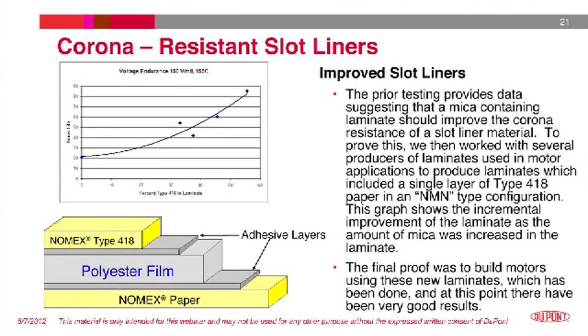We then worked with DuPont customers who already produced NMN laminates, and they produced a series of laminates where one layer of the NMN was replaced by Type 418 paper as a finished commercial laminate. This chart shows the incremental improvement seen in these laminates. Commercial motors were then built with versions of these improved laminates, and the good news is that there have been no failures to date. The bad news is that there have been no failures to date, so we don't know how much better these motors are than motors insulated with other slot liner materials such as NMN for the same application.